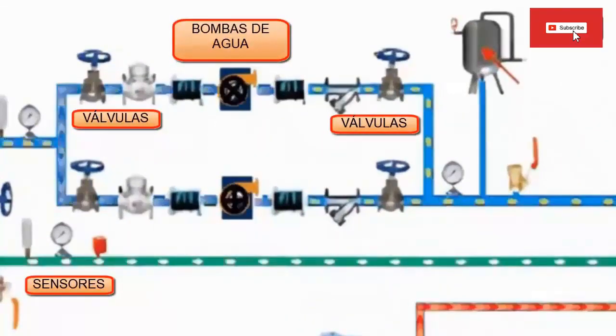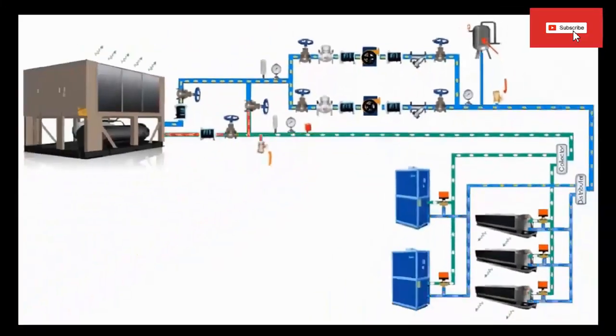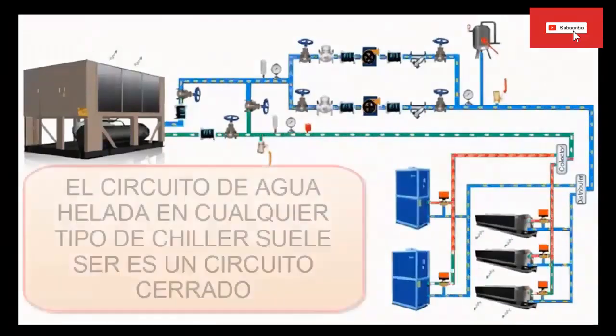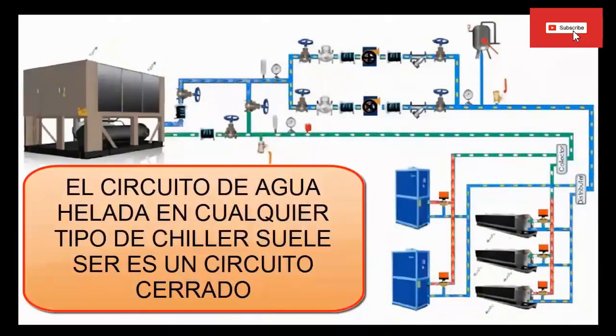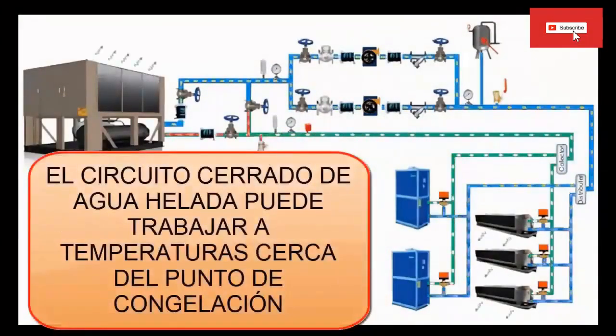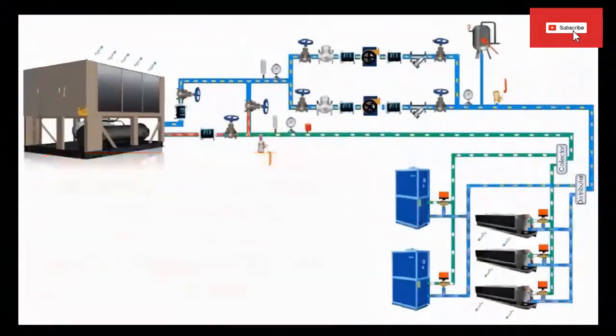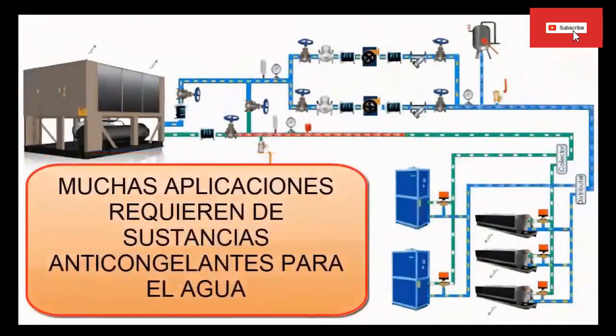The distribution of chilled water is a closed circuit, that is, it is not in contact with the outside air. This makes it much easier to maintain. However, there are industrial applications where the water temperature must be close to the freezing point, which requires the use of antifreeze substances for the water. So part of the maintenance is focused on keeping the water in appropriate conditions to avoid freezing at all times.